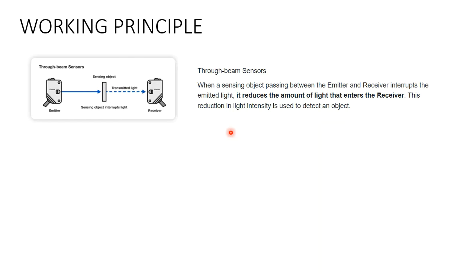As soon as there is interruption, it reduces the amount of light received by the receiver, and this reduction in light intensity is used to detect the object. The emitter and receiver are separate, and the part is introduced in between them, interrupting the continuous beam of light. The light can be infrared or red light depending on the sensing range.